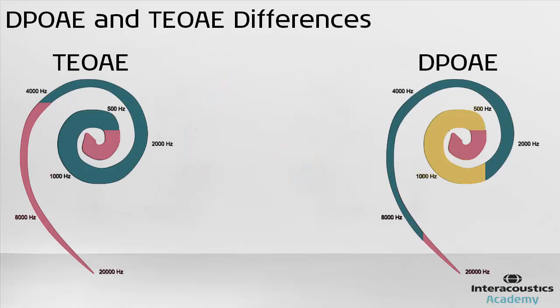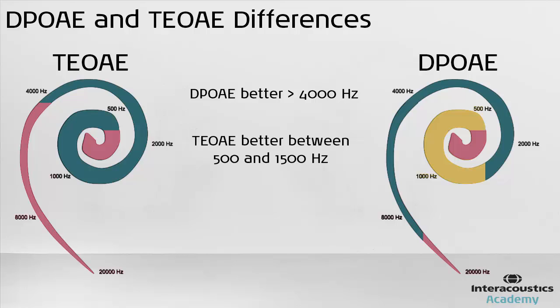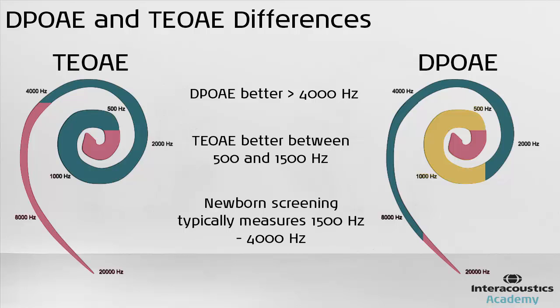Looking at the differences: firstly, DPOAE performs better above 4000Hz and TEOAE better between 500Hz and 1500Hz. However, these differences are less relevant for newborn hearing screening because most programmes screen at frequencies from 1500Hz to 4000Hz.